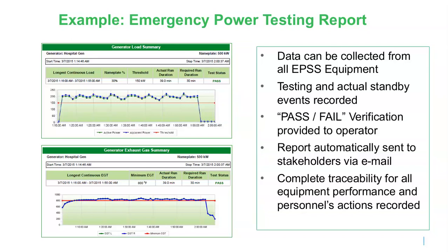There is another alternative method that's accepted by most AHJs, and it's certainly in NFPA 110: the generator exhaust gas temperature can also be used. So there could be instances where you're not able to reach 30%, yet your exhaust temperature may actually be above that minimum, which means that your monthly test would be a pass, and you would not necessarily be required to do annual load banking.